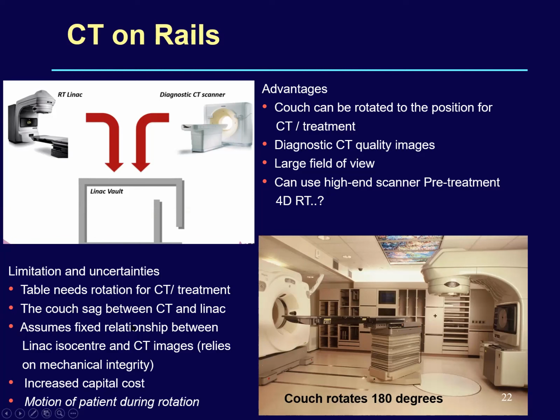Even a 4D CT can be done. But the disadvantage is that the couch sag between the CT and the LINAC is a problem, because when you rotate it and do a translational motion, assuming a fixed relationship between the LINAC isocenter and the CT images relies purely on the mechanical integrity. Further, putting two units in the same room is a capital cost, because very few CTs can be done on this, and you are going to treat 40 patients a day on the linear accelerator. So this becomes a little high cost and redundant. Motion of the patient during rotation is also a problem. When you rotate this couch 180 degrees, patients tend to move a bit.